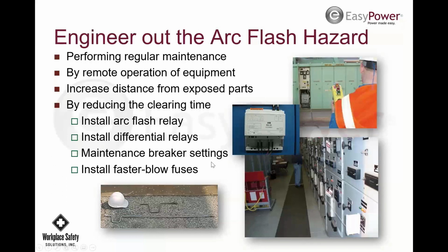Maintenance breaker settings. Sometimes if you have a maintenance setting, you can put the breaker down here on a lower trip time to bring down your arc flash level while you're doing maintenance and racking out breakers and stuff. The problem with that is it's now much more sensitive than breakers downstream. It's not coordinated anymore. So you could have a blow dryer in the bathroom cause the whole plant to go down, and you don't want that to happen. So it's a little risky.